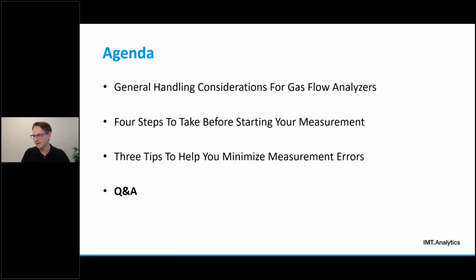Is it possible to set the start and the end trigger on different signals? Yes, most analyzers allow that. So you can, for example, if you have very specific or special situations where you see, oh, my pressure trigger is perfect for my start trigger and my flow trigger is better for my stop trigger, on most analyzers you can set a start trigger on the pressure curve and a flow trigger on the flow waveform.